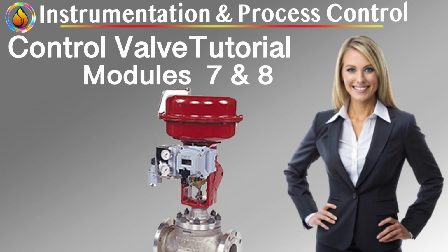This module is where paper specifications meet plant reality. A valve can be perfectly sized, correctly actuated, and equipped with a modern positioner, and still degrade control quality if its performance characteristics are misunderstood. Control engineers do not tune controllers against datasheets. They tune against valve behavior as experienced by the process. This is the final translation layer between design intent and operational truth.